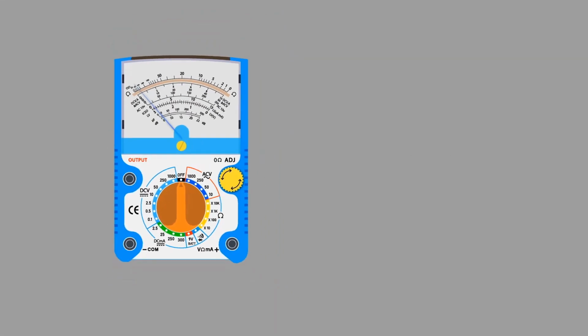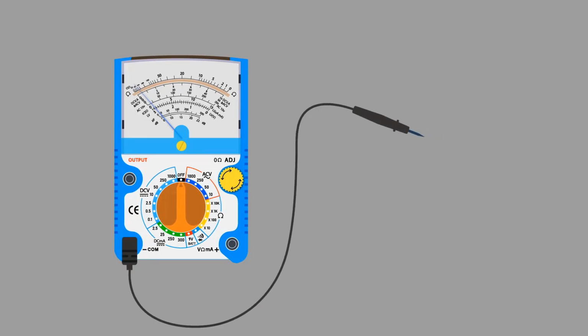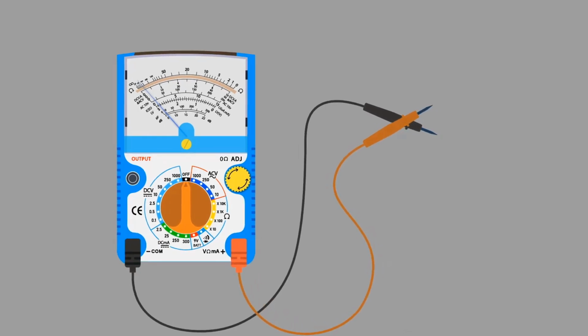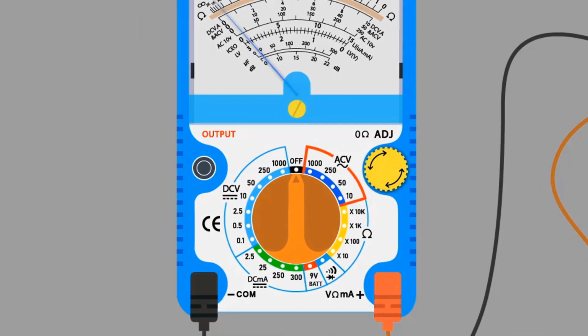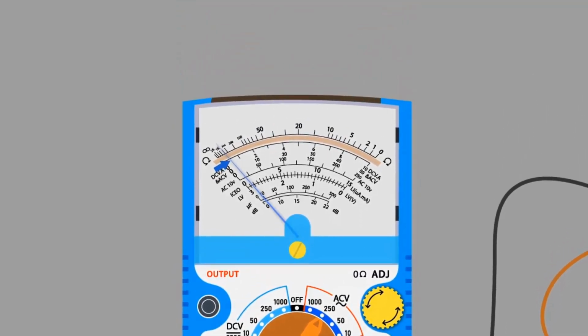Now we'll check AC voltage. Similarly, for AC voltage, we'll first connect the probes, one to the common terminal and the other one to the positive terminal. Now we'll move the dial to the AC voltage selection area, and we have set it to 250 volts. That is, the maximum voltage that it can measure is 250 volts. Now you can see again we have a zero error, so we'll use a screwdriver to fix that zero error.